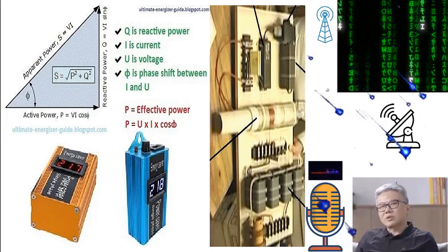Synchronous motors. In certain situations, switching from asynchronous to synchronous motors can provide greater efficiency and lower reactive power requirements, as synchronous motors offer better control over power factor correction. Transformer optimization. Underloaded transformers can be replaced with smaller ones to minimize reactive power loss. Properly sized transformers result in more efficient energy distribution and less reactive power demand.